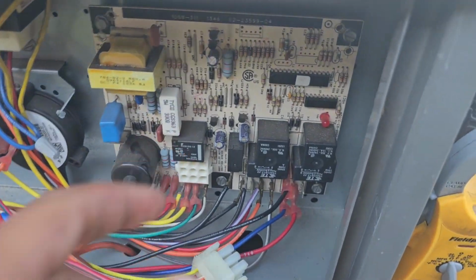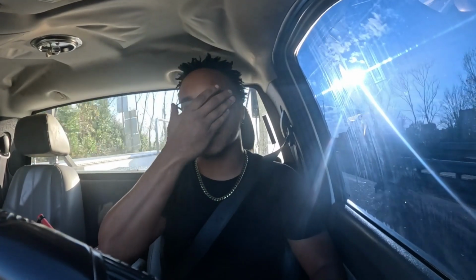That board is the issue here. Alright guys, so pretty much right there, I verified that the control board is not registering that the high limit switch is actually closed. It's not tripped at all, which means the board is the issue in this situation.